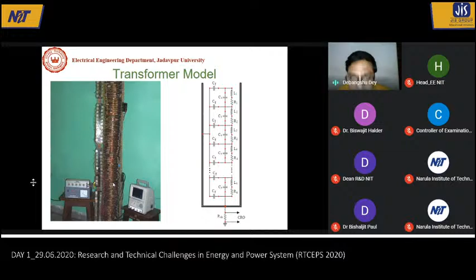So condition assessment means we are trying to find out, is there any fault in the winding? Are there different turns of the windings in the transformer that have suffered insulation failure, or are short circuited? How? By looking into the current waveform. Just look there. Say this is the winding, and the winding will have some turn to turn capacitance and some capacitance between the winding and the ground. So CS means the turn to turn capacitance, and CG the capacitance to ground. Now if a fault occurs, what will happen? That capacitor will be short circuited, so there will be no such CS, only CG will be there, so there will be some change in the circuit.